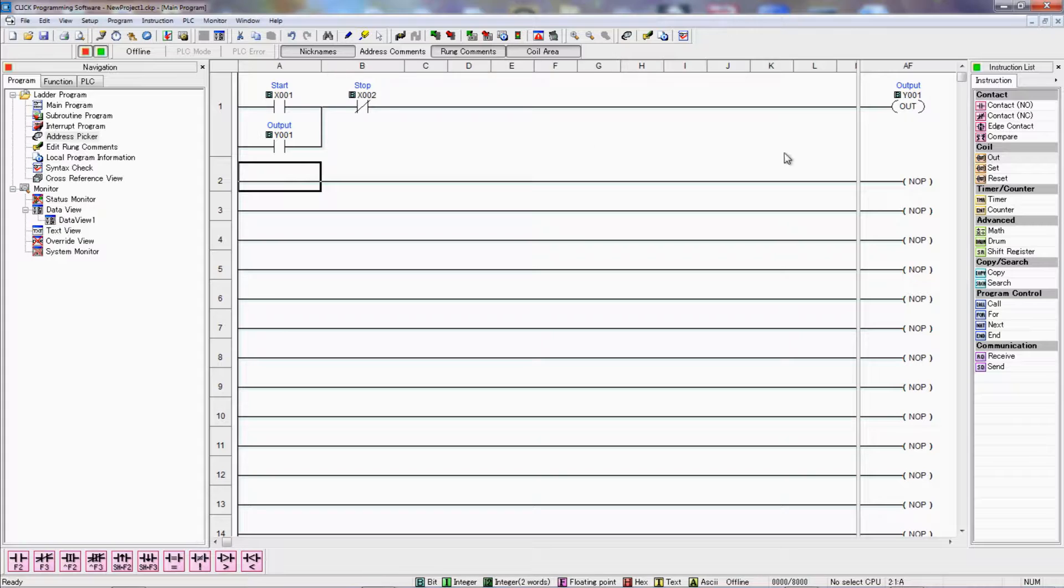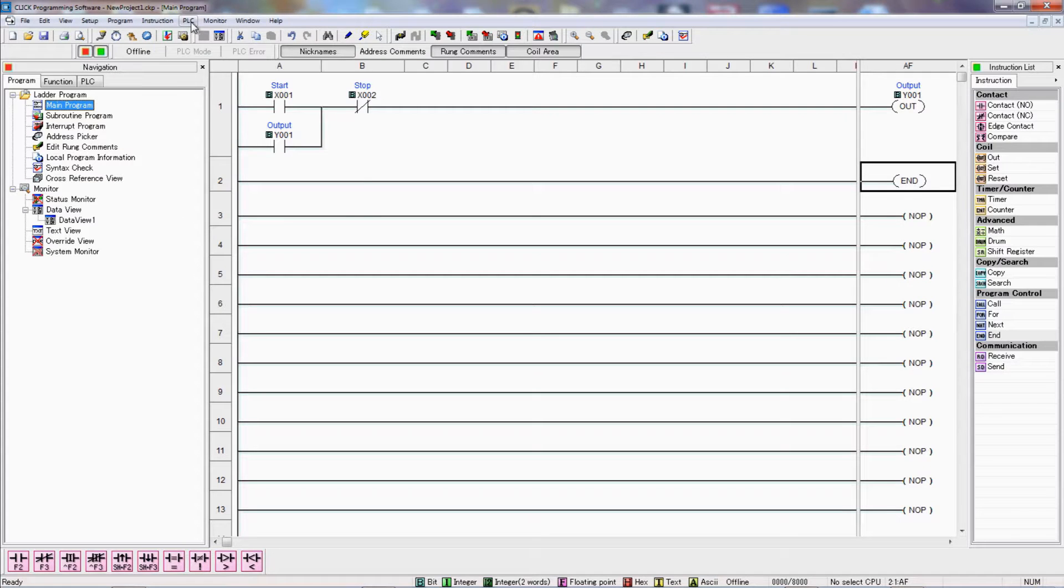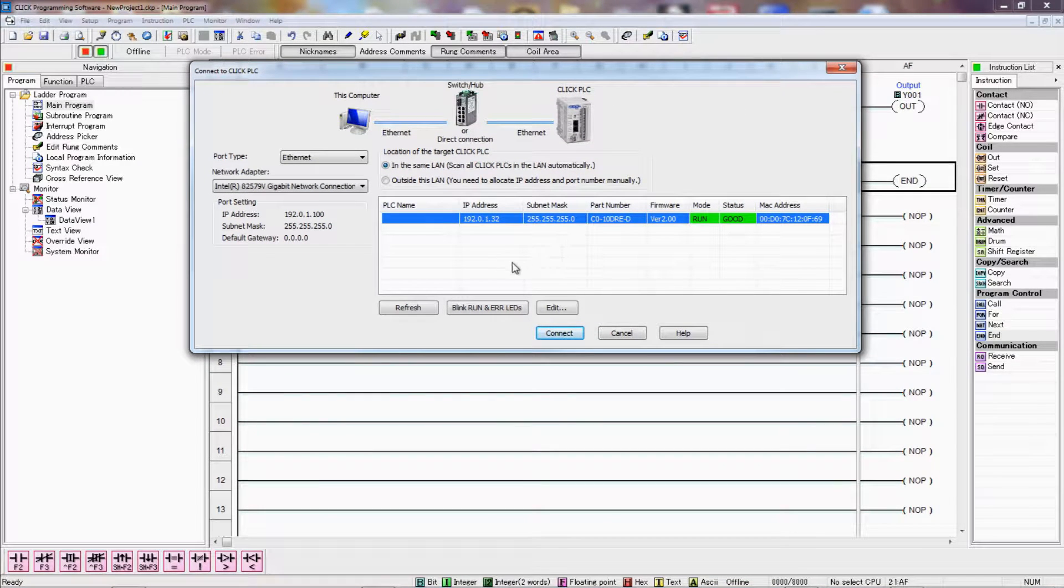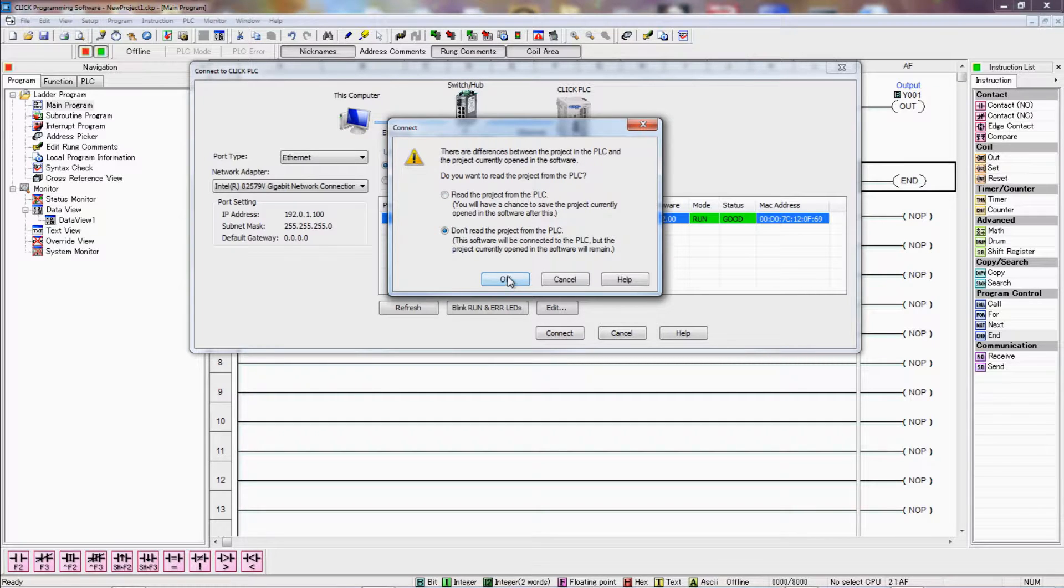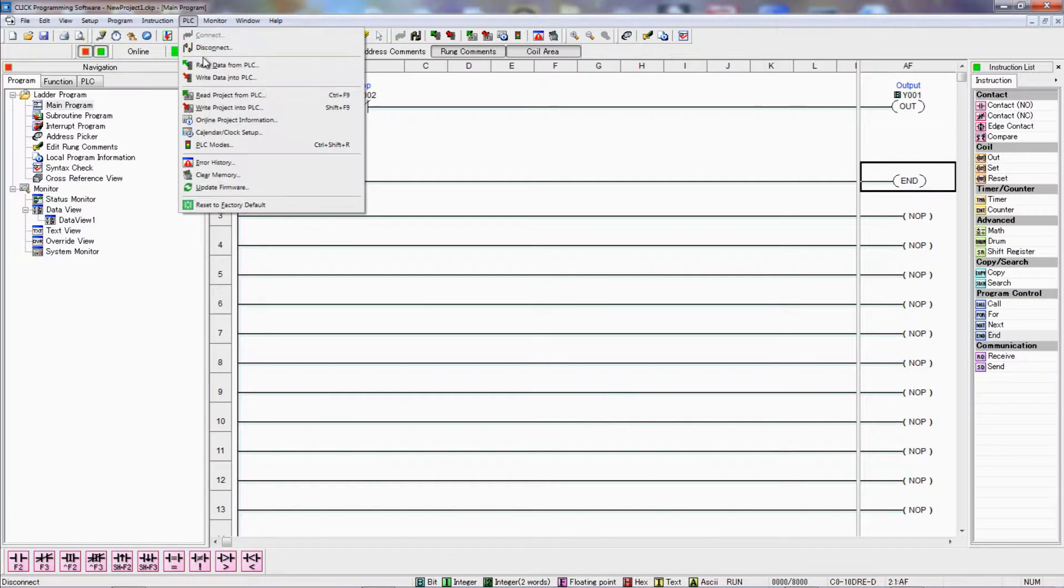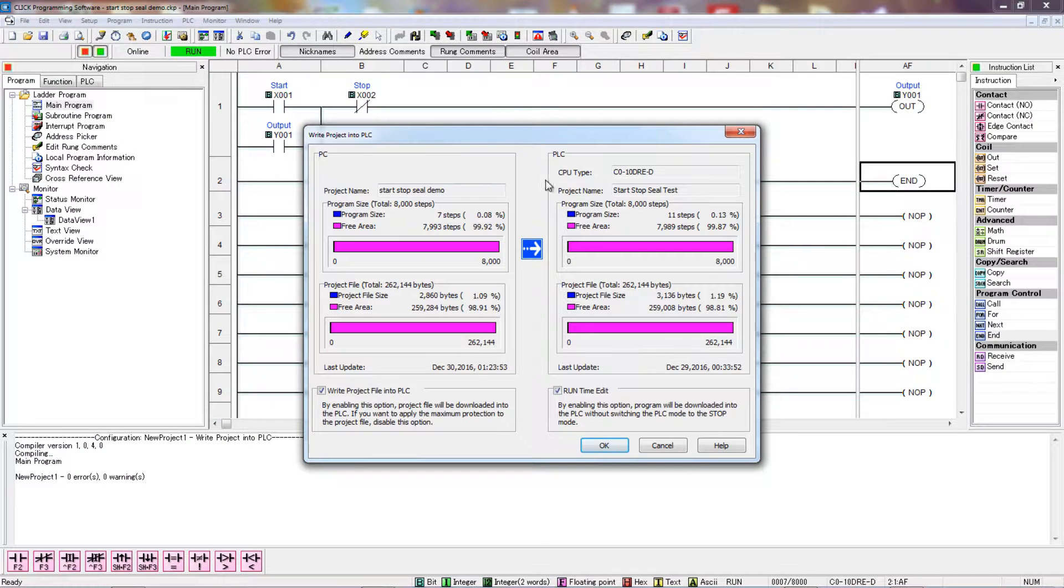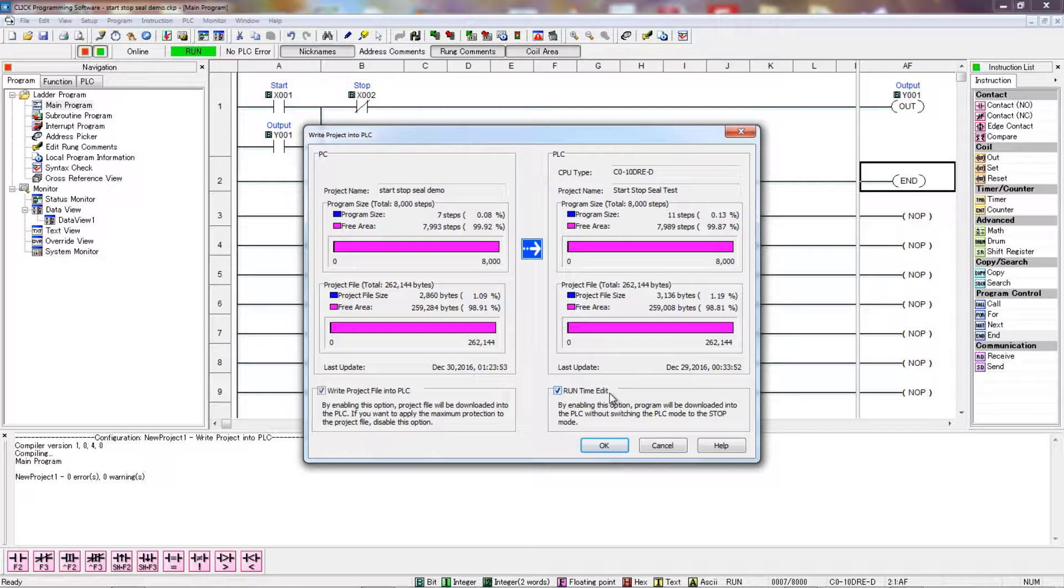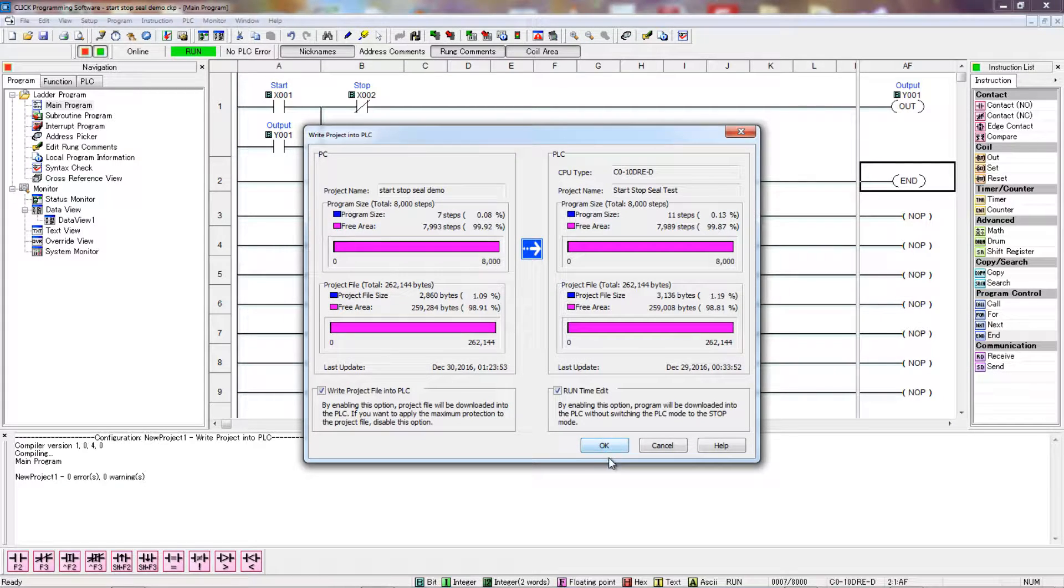So I need to add a little something here before we can download this to the PLC. You just need an end instruction. So we're in the main program area here, and we always need to have an end instruction. We'll connect to our PLC. And I'm using an Ethernet version of the Click PLC. We'll connect up. Typically, you don't want to read the project from the PLC if you're just constructing a project for the first time. And now I will go to PLC and write project into the PLC. Showing me the size of the program. I'm also doing a runtime edit, so I can download it in real time. This is mainly focused on the start-stop-seal circuit, so I'm not going into depth too much on all the little idiosyncrasies of the Click programming. If you'd like to see that in a future video, let me know.